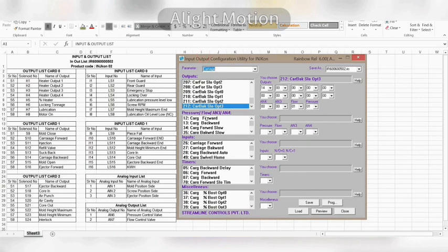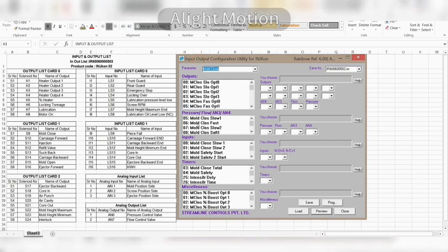Now our second step is pressure, flow, AN3, AN4. Our list has two proportional outputs, such as pressure and flow. So now we know about that. First we selected mold close in the parameter. We enabled pressure and flow in the output first, but here is to select its channel. Here the channel number of pressure is 1, and the channel number of flow is 2.